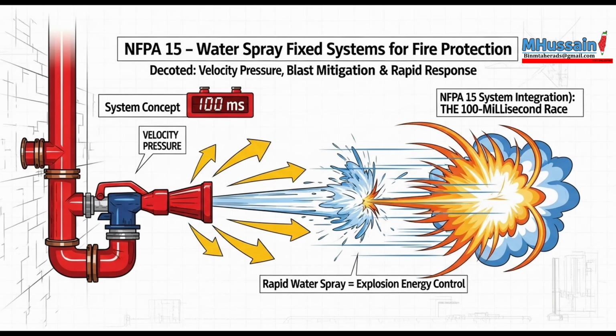Okay, let's shift from the mandate to the actual mechanics, the hardware, the materials themselves. For systems handling high pressure, maybe operating in explosive atmospheres, surviving extreme heat, standard parts just won't cut it, right? Not at all. So what does NFPA 15 demand for pipe and fittings? Section 5.3.1. We're looking at pretty strict standards here. The requirements point to various schedules of ferrous piping, schedule 10, 30, 40, plus stainless steel pipe and copper tube. And crucially, these all reference specific ASME standards like B36.10M and B36.19M. That governs wall thickness, material quality. Ensuring durability. Exactly. Durability under both static pressure and the high dynamic pressures during activation.